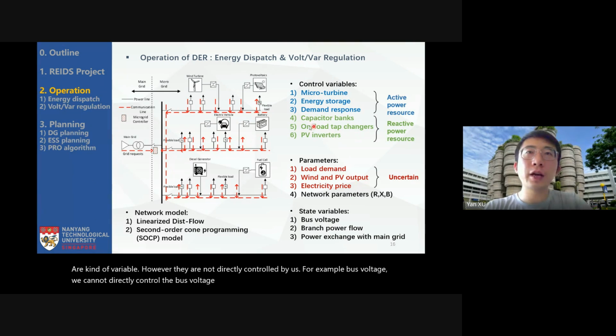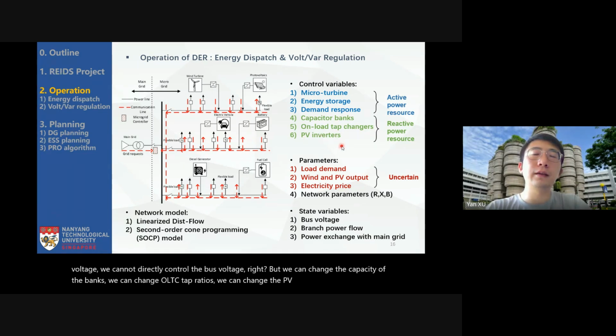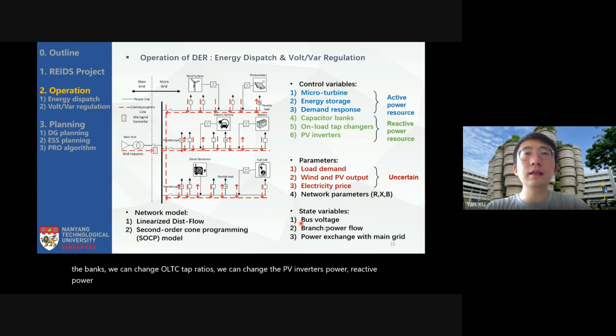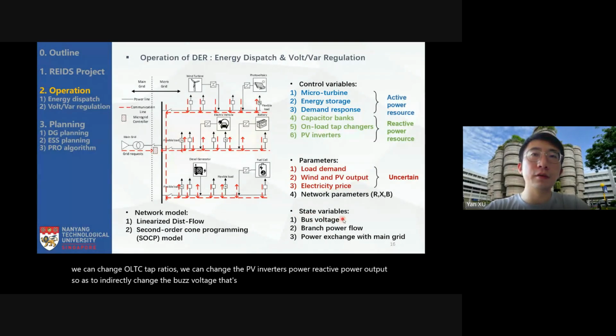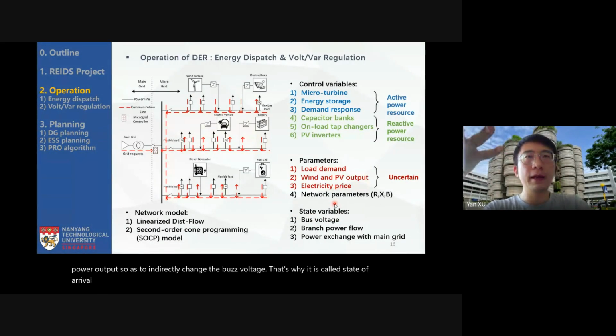But we can change the capacitor banks, we can change OLTC tap ratios, we can change the PV inverter's reactive power output, so as to indirectly change the bus voltage. That's why it is called a state variable, because its value depends on other control variables.